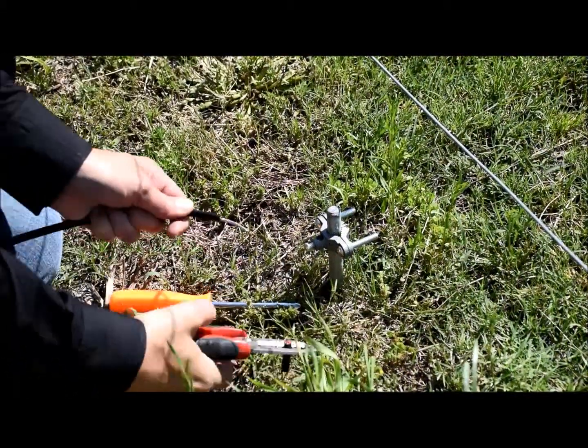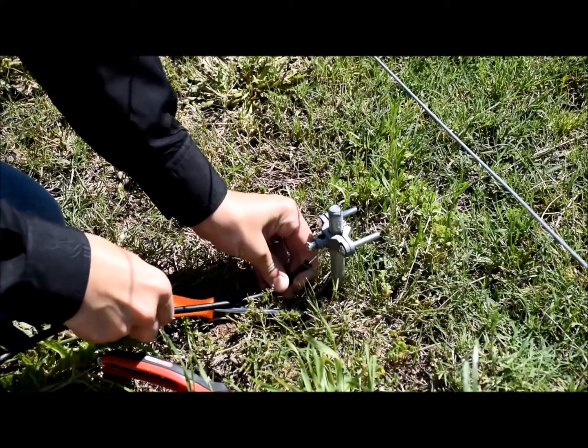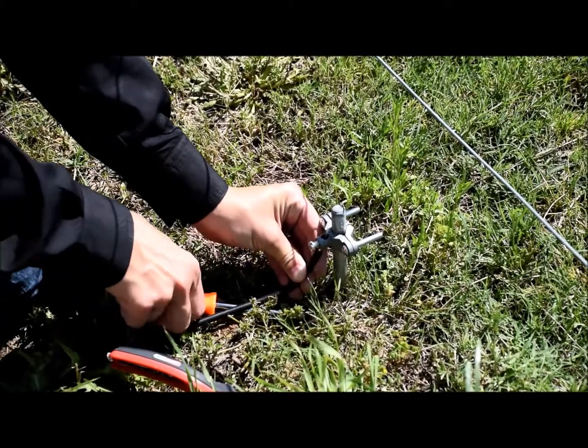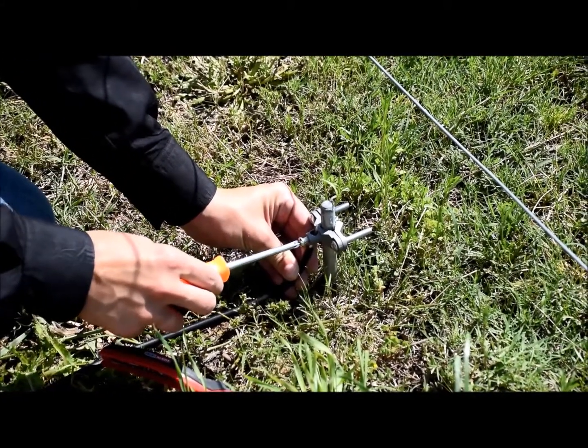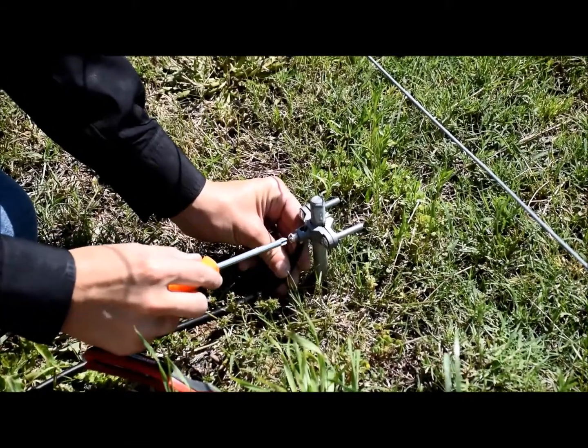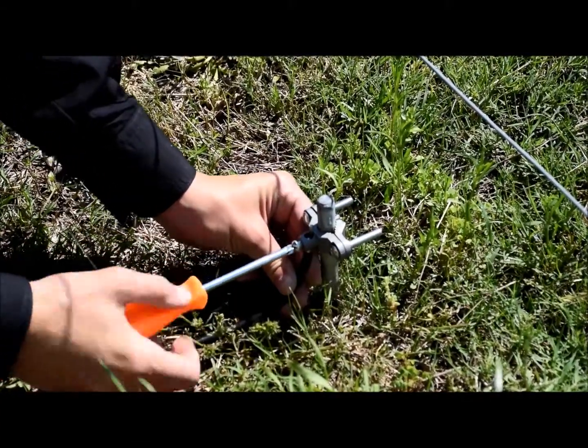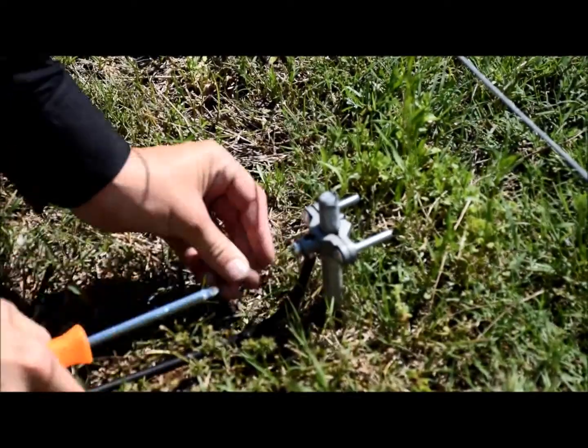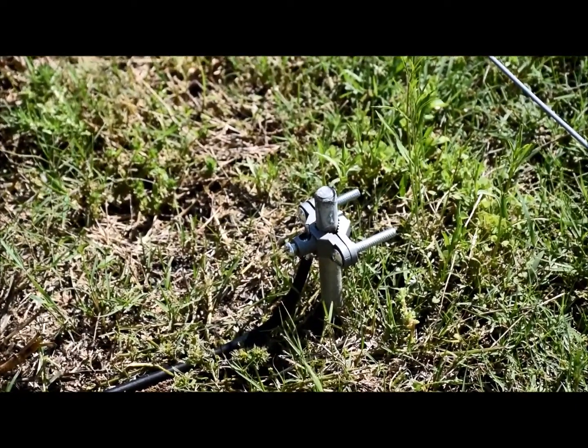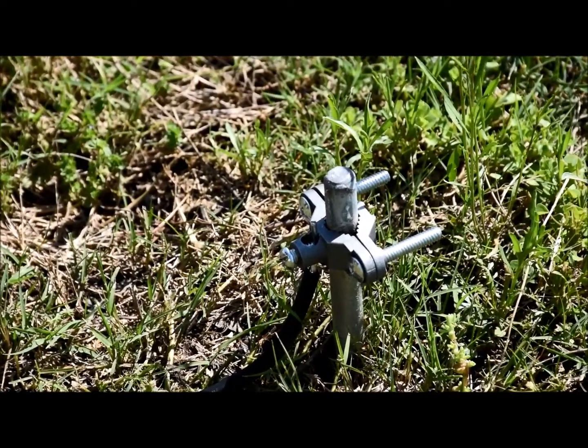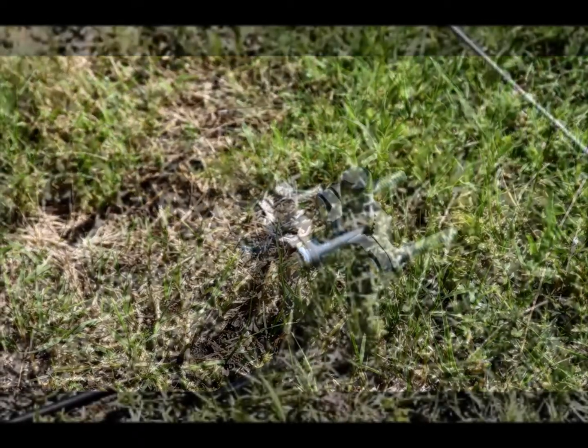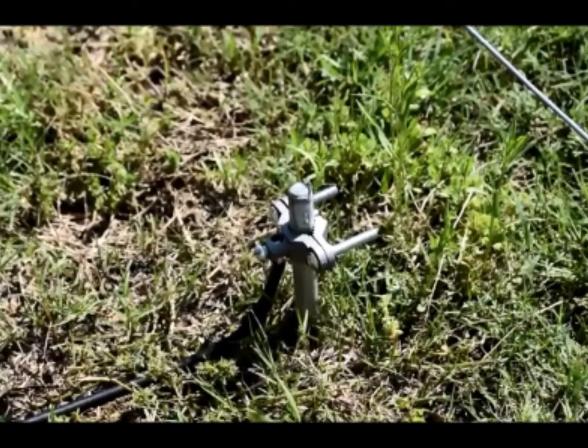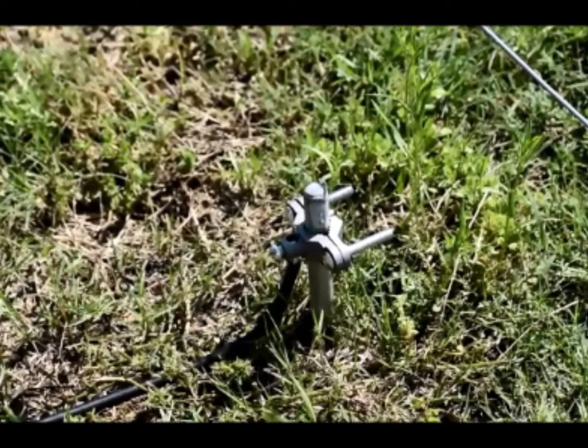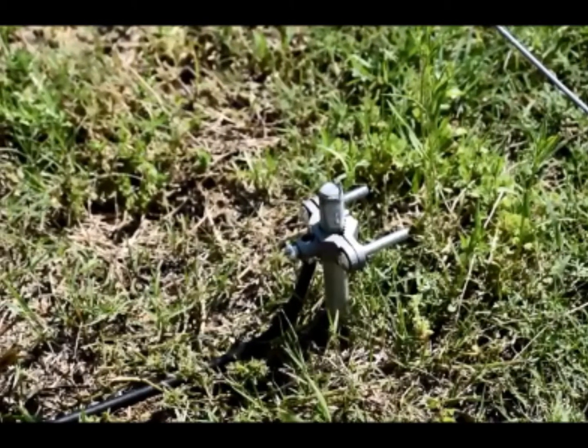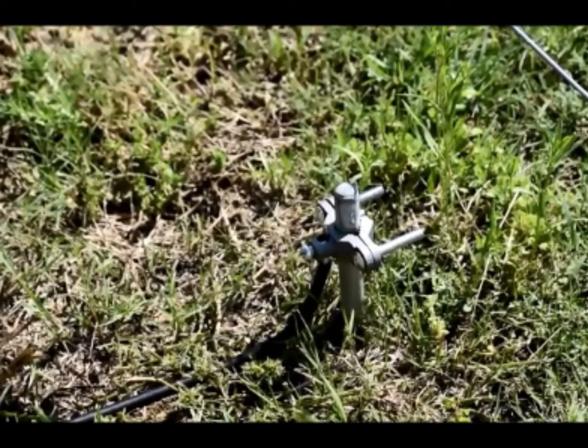Then use the wire strippers to remove approximately 1 inch of the coating at one end of the underground cable. Insert this exposed end of the underground cable into the section of the ground rod clamp with a small hole and center screw. Insert the cable so that the exposed end is pointing up to the sky and not towards the ground. Tighten the center screw on the ground rod clamp to secure the underground cable wire.